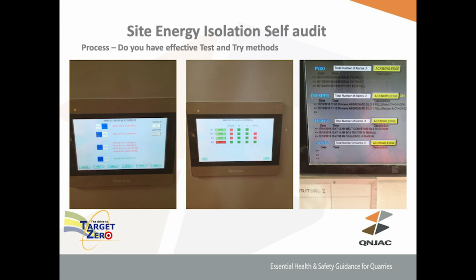So you would stop the sequence, put the sequence into manual, then go to the device and start and stop it from that HMI screen. When you do that for test and try, an alarm comes up on the SCADA saying, for example, Ambuco BC5 tested in manual and sequence in manual. For test and try purposes, the only real way of doing it is to run the piece of equipment, isolate it, and then run it again.